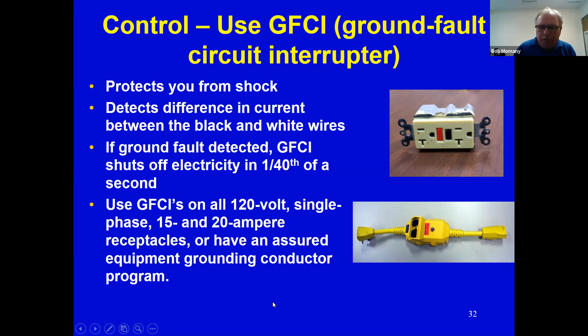So anytime that I have an area that's considered wet, a bathroom area, a sink area, maybe like a mop sink in a janitorial area, all of that needs to have ground fault circuit interrupters in it because of the damp, wet area. And in construction, everything is supposed to be ground fault circuit interrupter protected. So either everything is supposed to be plugged directly into a GFCI, or they're plugged into what you have at the bottom here, a GFCI extension cord, which I can plug into a standard outlet, but will still give me the GFCI protection. So those are wonderful tools that are lifesavers.